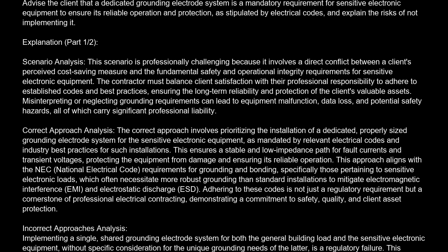This ensures a stable and low impedance path for fault currents and transient voltages, protecting the equipment from damage and ensuring its reliable operation. This approach aligns with the NEC (National Electrical Code) requirements for grounding and bonding, specifically those pertaining to sensitive electronic loads, which often necessitate more robust grounding than standard installations to mitigate electromagnetic interference (EMI) and electrostatic discharge (ESD). Adhering to these codes is not just a regulatory requirement but a cornerstone of professional electrical contracting, demonstrating a commitment to safety, quality, and client asset protection.